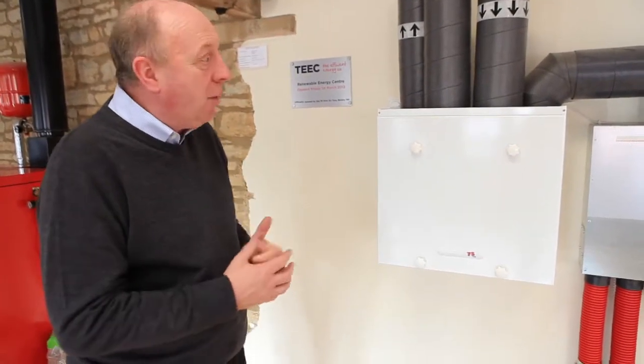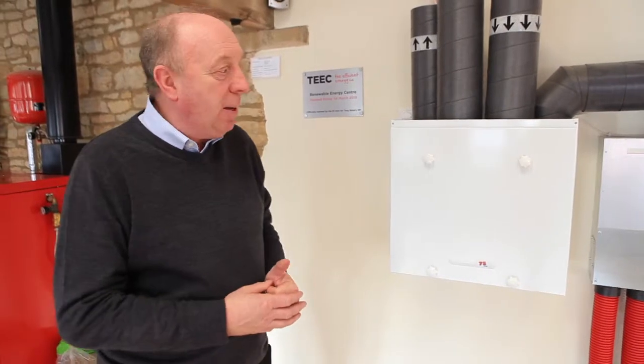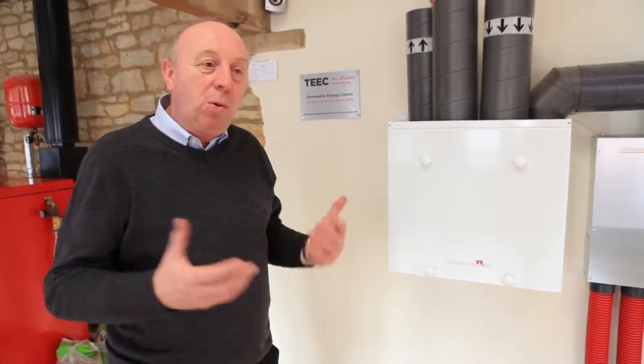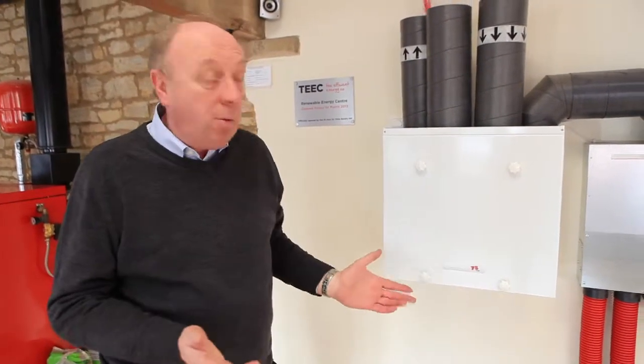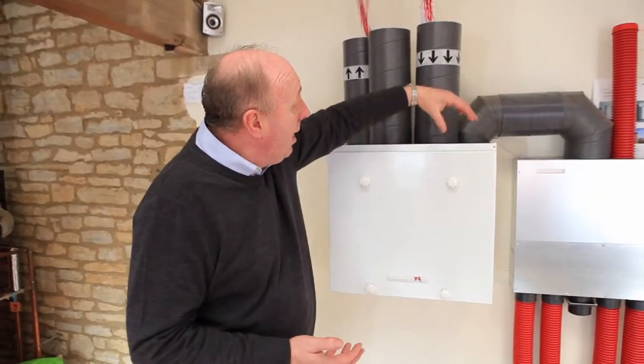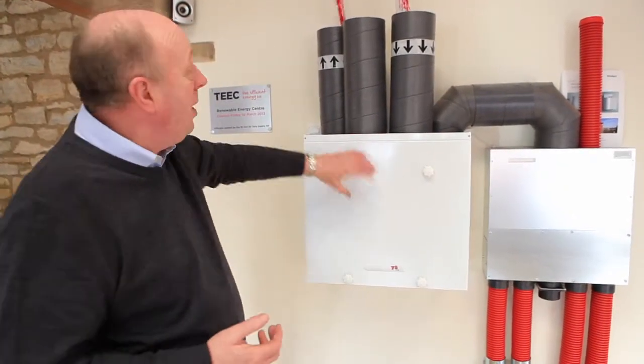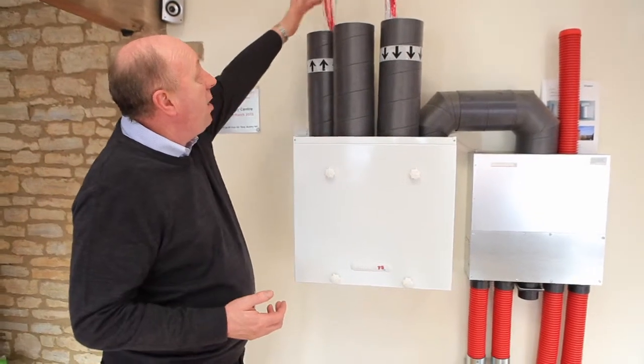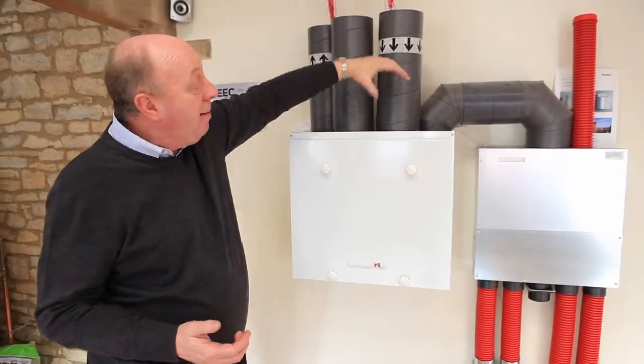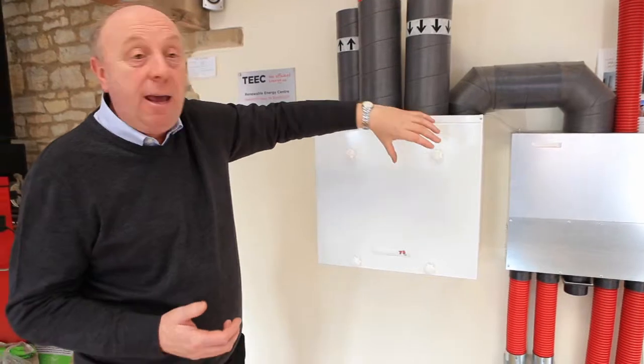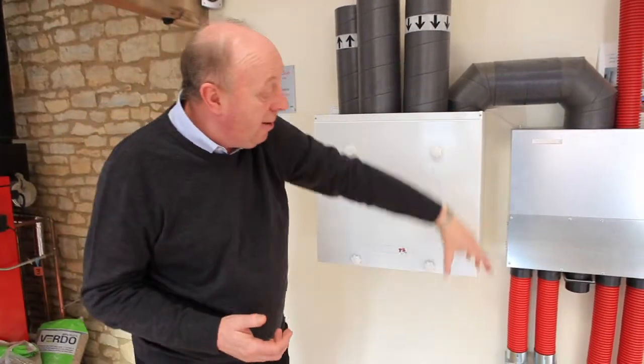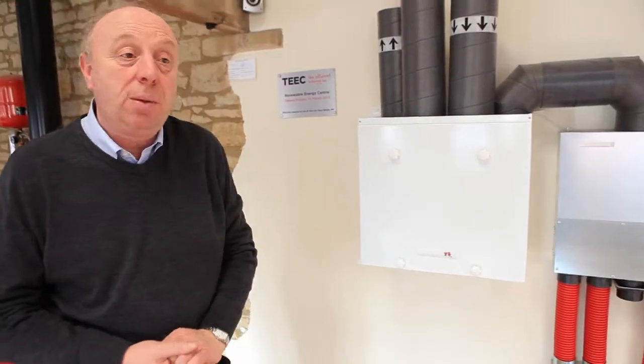And in the summer, we still need to extract from the building, but do we really in the summer want to put warm air back in the building? We don't. So what we do is the extracted air comes back in. It still goes over the heat exchanger and back out to the atmosphere, but the internal air then bypasses the heat exchanger. It picks up none of that waste heat, and it delivers cool air back through into the building.